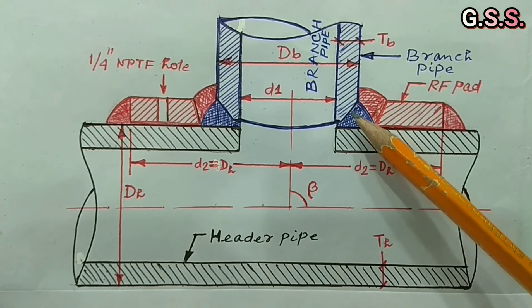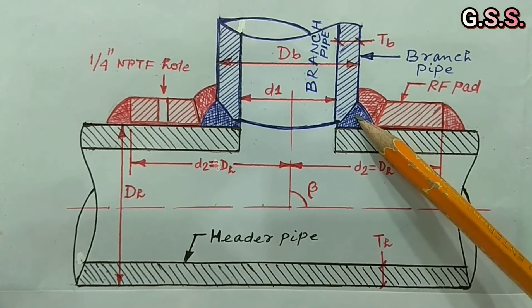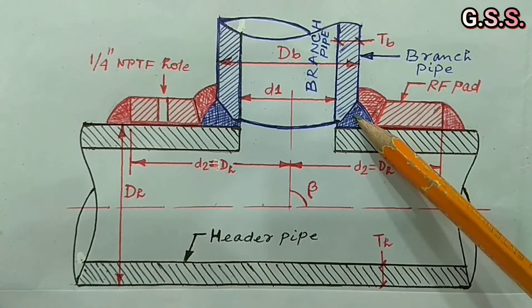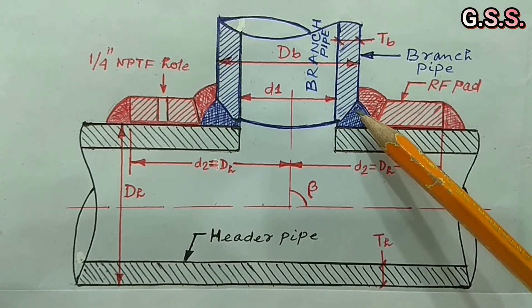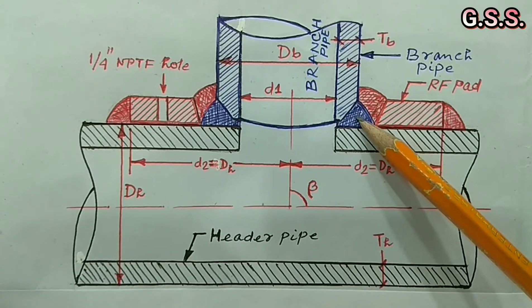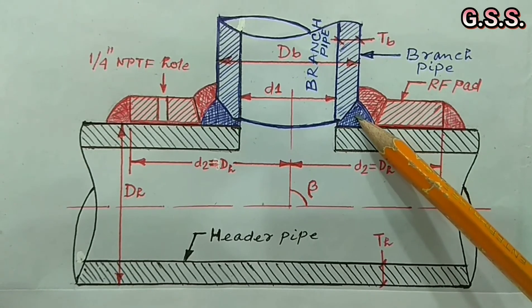Because SIF means stress intensification factor of butt welding is 1 whereas SIF for fillet welding is 1.3. That means 30% more stress is developed in direct branching.